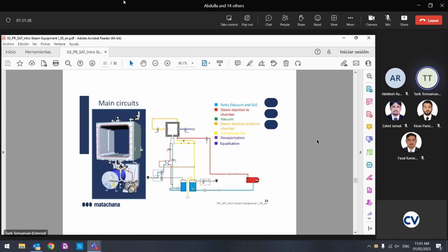Then the other line is the devaporization. The devaporization is the line going to the heat exchanger, and we use this circuit after the sterilization plateau. Once we finish the sterilization, we remove all we have in the chamber, but we do it through the heat exchanger. Remember, in the Serial 1000 there is a heat exchanger; in the 500 there is not, and it goes directly to the vacuum line. Then we have the equalization. Equalization is after the drying, so we have to return to atmospheric pressure. How to do that? By admitting air into the chamber to reach atmospheric pressure. Okay? This is the service.